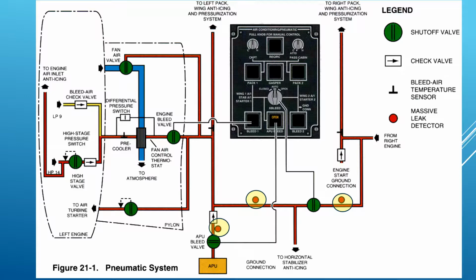And what we're aiming for is a bleed air temperature downstream of the pre-cooler of around 200 degrees C. If the bleed temperature rises, the fan air valve opens up a little bit more, allows more fan air, cooling air to come through, bleed air temperature will drop. So it just modulates that fan air valve so that downstream of the pre-cooler, we've got approximately 200 degrees C.